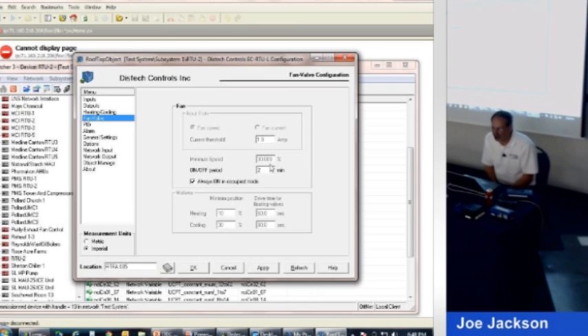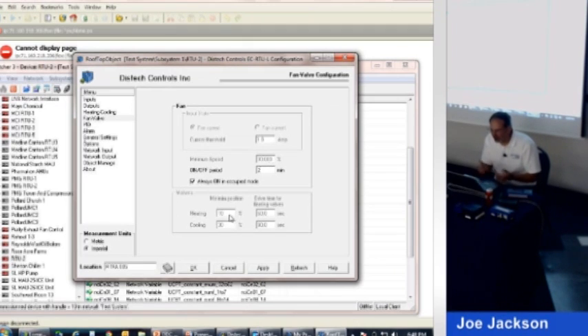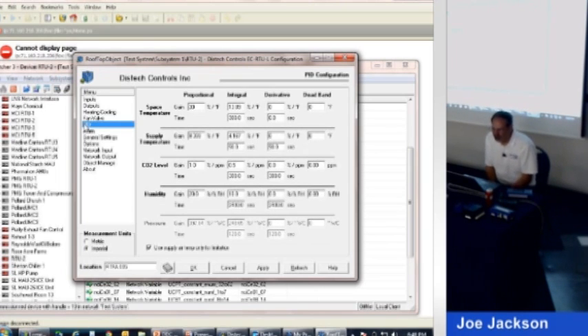If you were doing a variable speed fan on a VFD or something, and you don't want the fan speed to drop below 30%, you could apply that here. Once the fan shuts off, it stays off for 2 minutes. This is only if you have valves on your system, a chill water valve, a hot water valve. It doesn't apply to us. It's grayed out. PID, that stands for proportional integral derivative. They're all set. You don't have to mess with them.